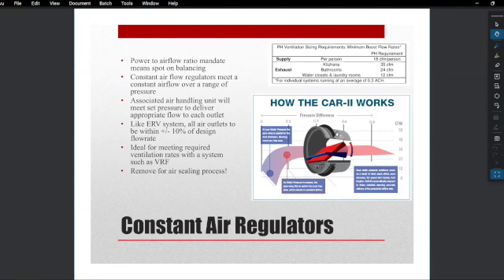You have to make sure you isolate all of your dampers, any fire dampers, fire smoke dampers, motorized dampers, CAR dampers, because obviously this stuff is going to coat them, and it's going to affect their functionality. And at the air outlets themselves, it's really important that those air outlets in the apartments are blocked up and sealed, and that the CAR damper is removed.